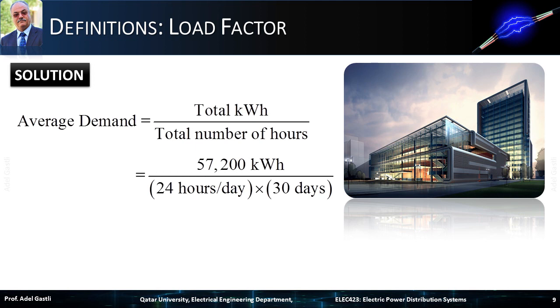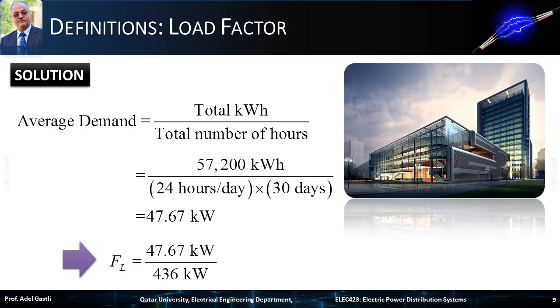To calculate the load factor, we first determine the average demand: 57,200 kilowatt hours divided by 24 hours per day times 30 days per month, which equals 47.67 kilowatts. Therefore, the load factor is the ratio of the average demand of 47.67 kilowatts divided by the maximum demand of 436 kilowatts, times 100%, which equals 18.22%. As you can notice, this is a low load factor, indicating that the maximum demand occurs only occasionally.